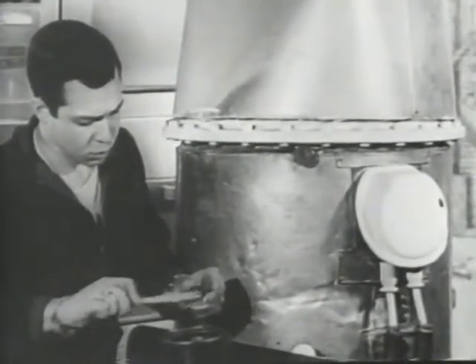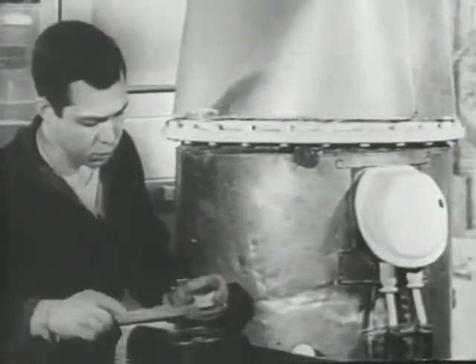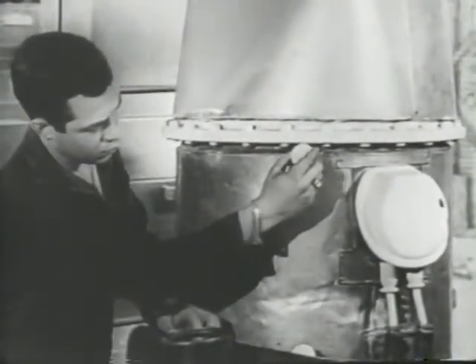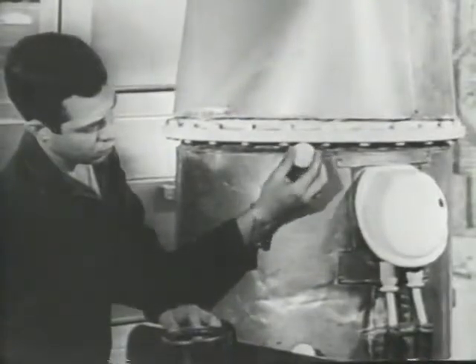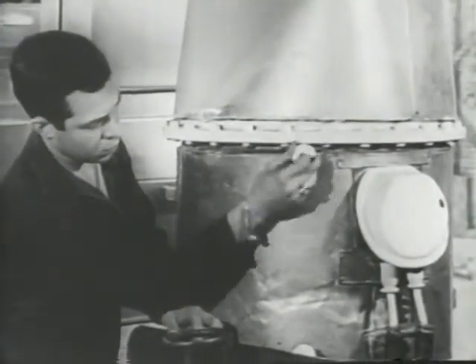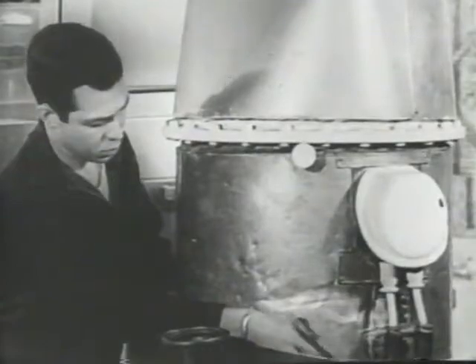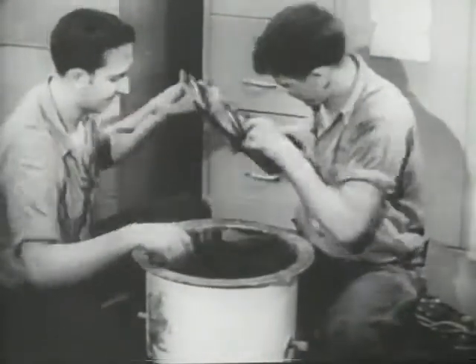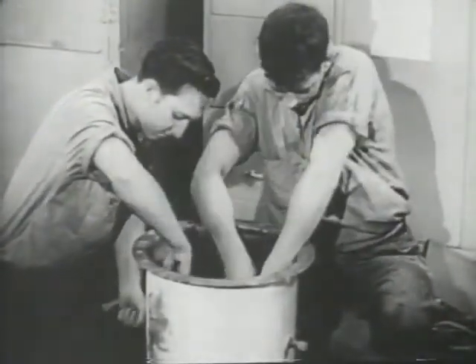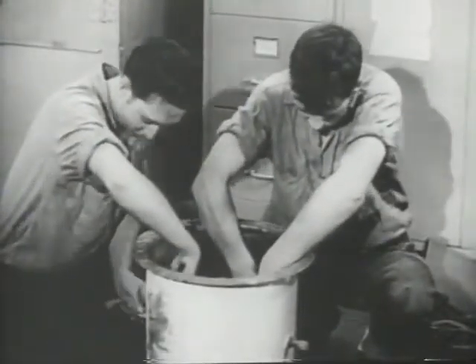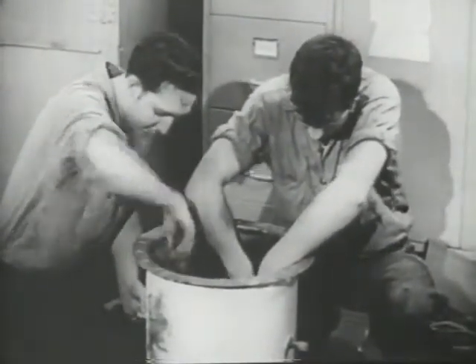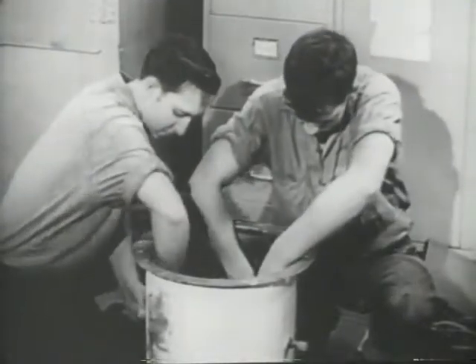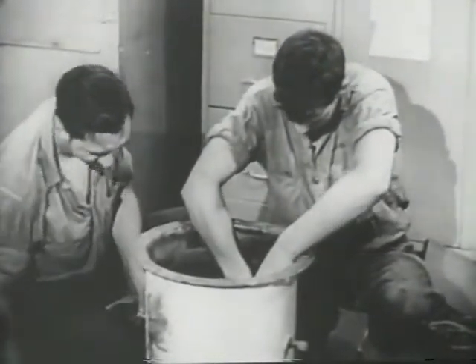In many cases, new fans have been in storage for months or even years, thus causing possible deterioration of the lubricating quality of the grease. If unchecked, bearing and motor failures will result. Only authorized personnel should maintain, adjust, and repair the air conditioning system. Unauthorized personnel should never attempt to obtain additional cooling effects by piercing ductwork. This may create a serious hazard where watertight ductwork is involved.